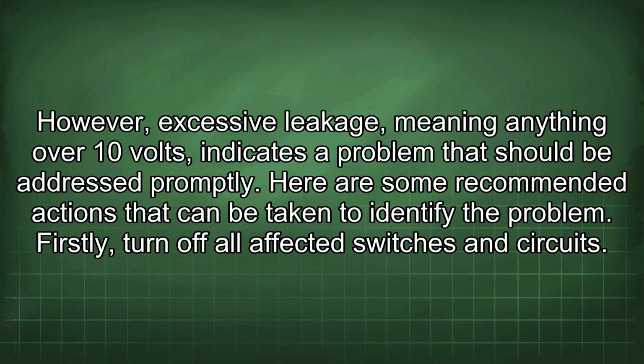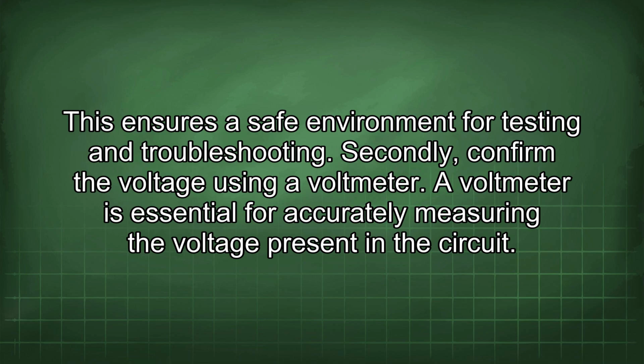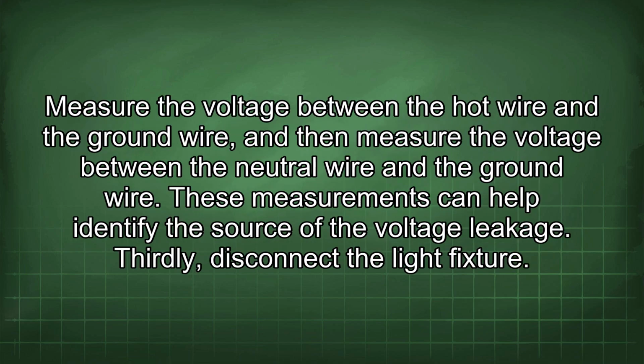Here are some recommended actions that can be taken to identify the problem. Firstly, turn off all affected switches and circuits. This ensures a safe environment for testing and troubleshooting. Secondly, confirm the voltage using a voltmeter. A voltmeter is essential for accurately measuring the voltage present in the circuit. Measure the voltage between the hot wire and the ground wire, and then measure the voltage between the neutral wire and the ground wire. These measurements can help identify the source of the voltage leakage.